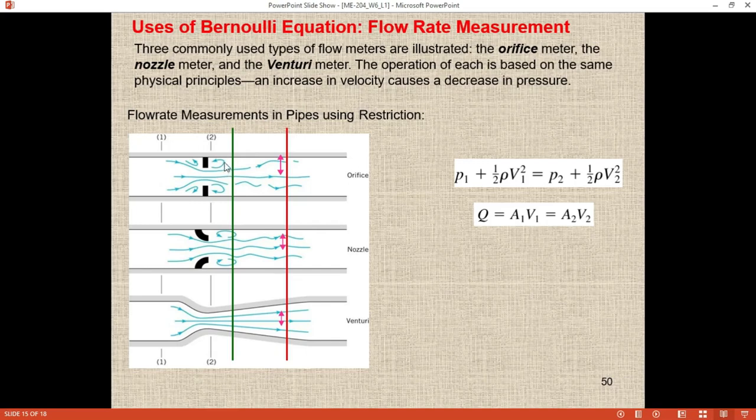So here you can see the cavitation space. If you have a sensor here, you will not get a right reading. You will get some reading, but it will not be accurate, appropriate, or trustable. If you take the nozzle section, in the orifice the fluid layers are separated from each other.